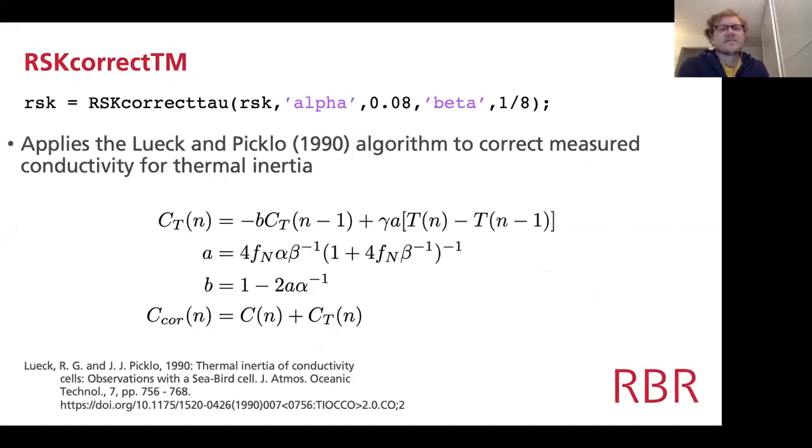We have a function that applies the Lueck and Picklo algorithm to correct for thermal inertia of the conductivity cell. The algorithm is here, and this is all in the paper that's listed below.